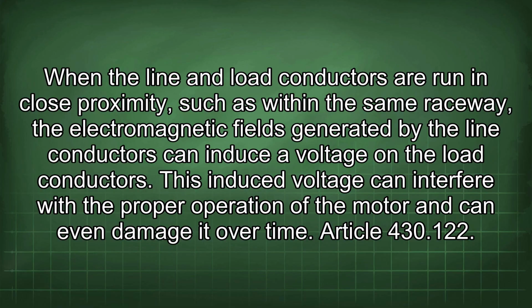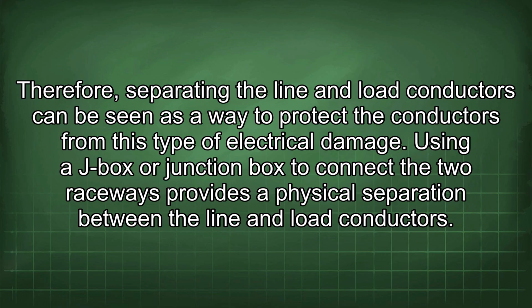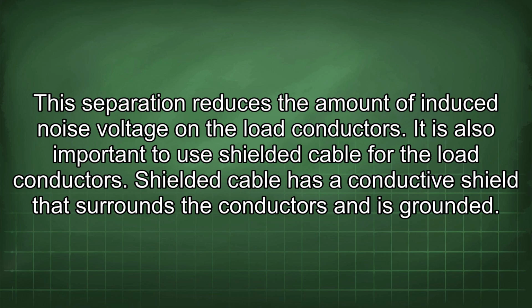Article 430.122 of the National Electrical Code emphasizes the importance of protecting conductors from physical damage. While the induced noise voltage may not be considered physical damage in the traditional sense, it can certainly lead to premature failure of the motor and other equipment. Therefore, separating the line and load conductors can be seen as a way to protect the conductors from this type of electrical damage. Using a J-box or junction box to connect the two raceways provides a physical separation between the line and load conductors. This separation reduces the amount of induced noise voltage on the load conductors.